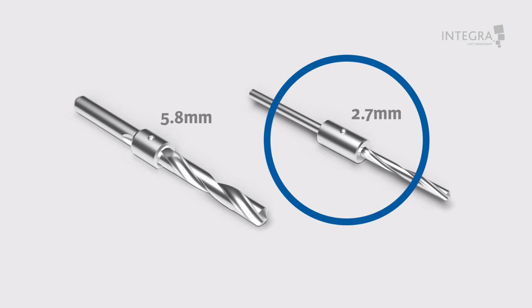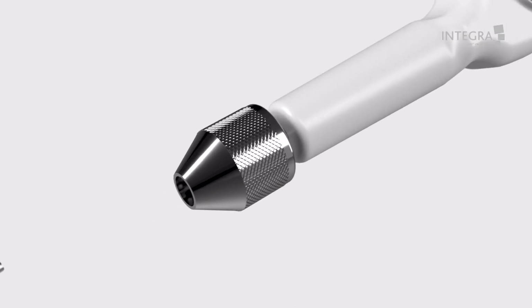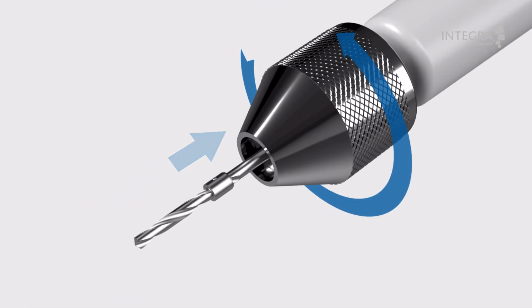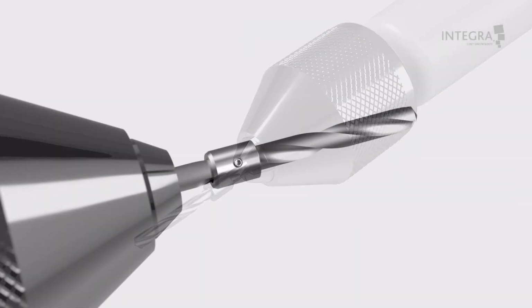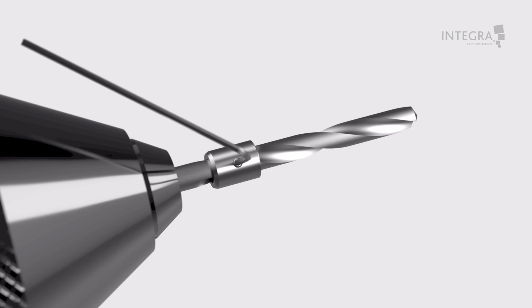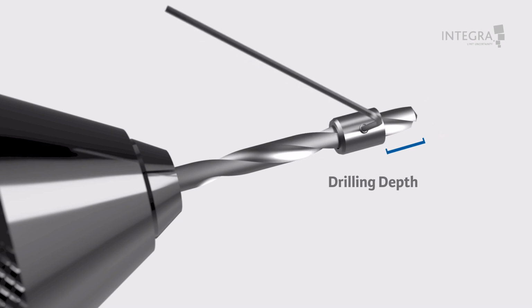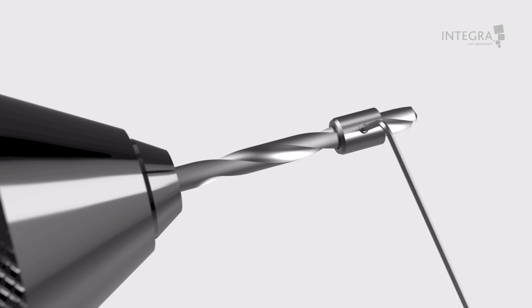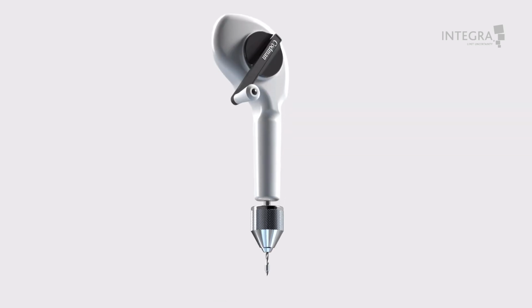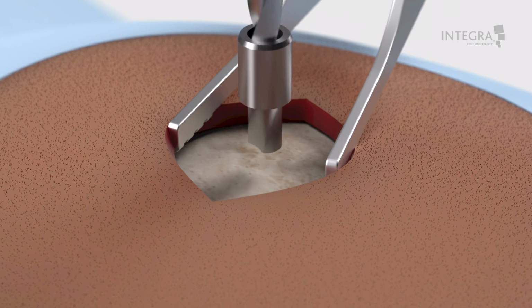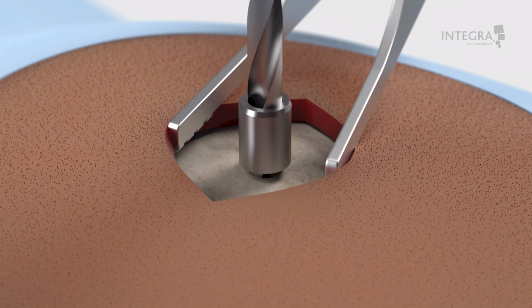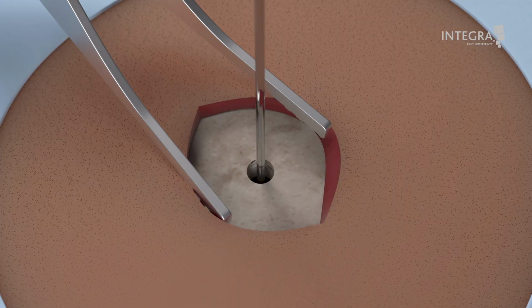Now select the 2.7 mm drill bit for subdural and intraparenchymal procedures. Place the bit into the chuck, then hold the drill handle in place and turn the chuck counterclockwise to tighten the bit. Next, loosen the drill depth guide with the appropriate hex wrench and carefully slide the drill guide towards the tip of the bit until the desired skull depth is reached. It is important to note that the drill guide will not stop the drill. It is designed only to provide the neurosurgeon with a marker for drilling depth. Finally, tighten the drill guide in place with a hex wrench and begin drilling. Open the dura with an appropriate needle or blade.